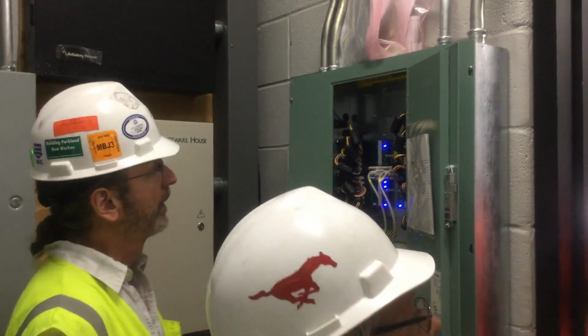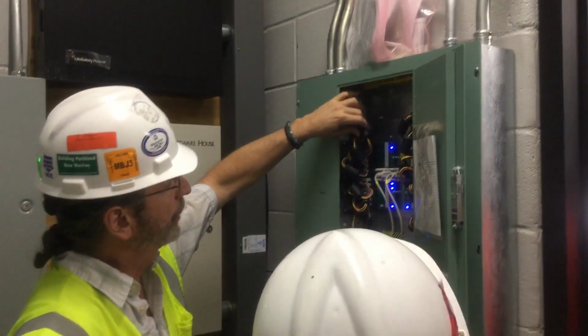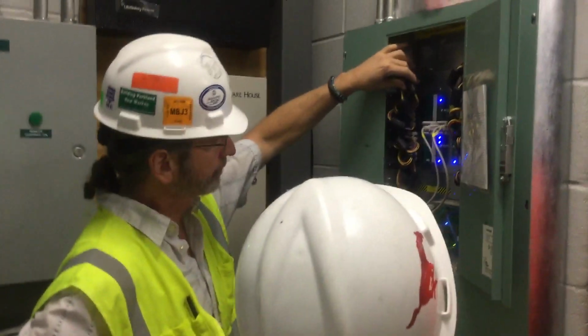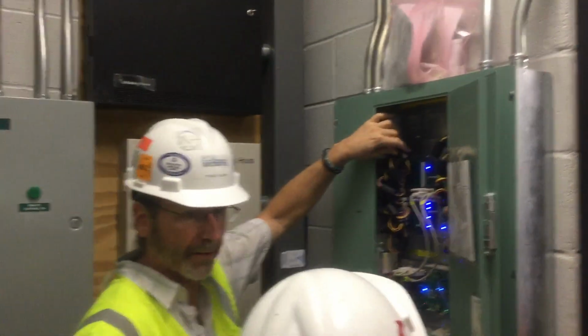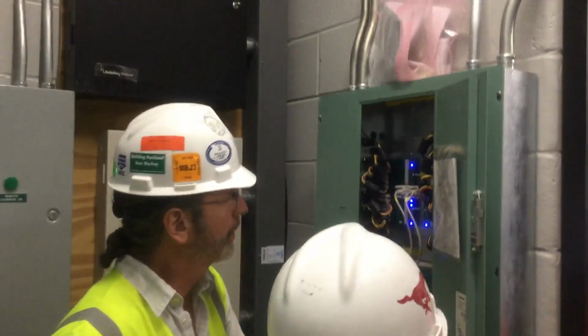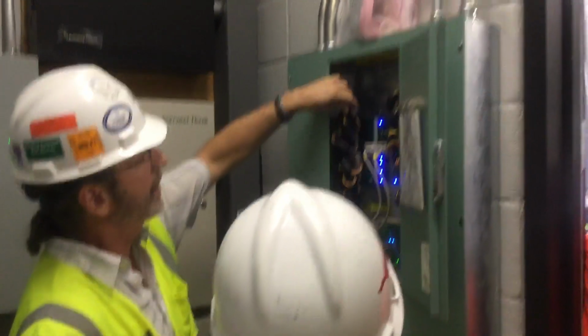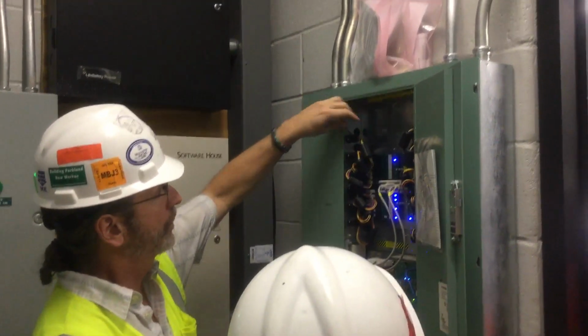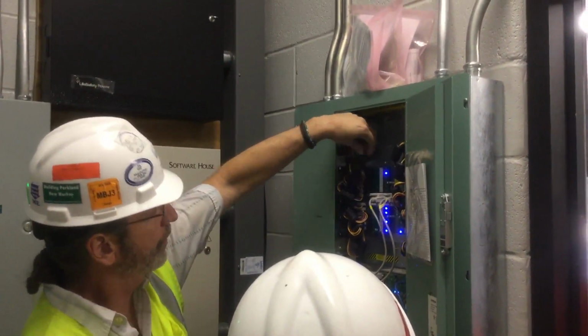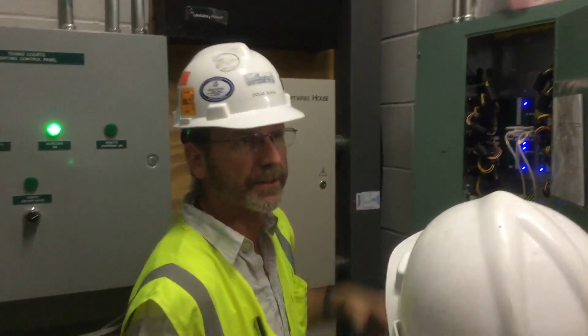We have these little ferrite filters on the relay control wires to keep noise from inducing back on the board. So if you ever change out a relay, you can pop this ferrite coil off, put it on the new cord, or just unplug the control wire from the relay, change the relay, and plug it back on. That's about as easy as it gets.